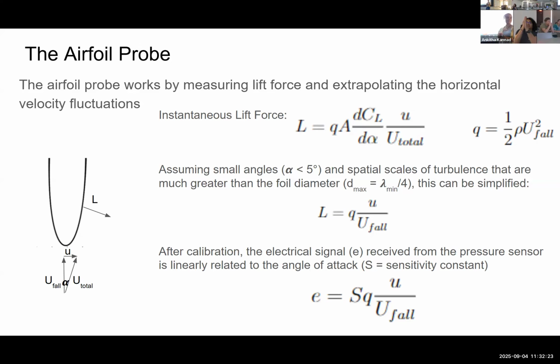And so your piezoelectric is like the diameter of that foil, and you're trying to figure out how much it's shifting with that voltage difference, right? Yeah, I should have included a slide on this, because I did a whole model. As the fluid passes over the silicone, which is the outside skin of this probe, it exerts a pressure on that skin. That pressure is translated through the material and creates a bending stress inside of the material. Now I wish I had the slide.